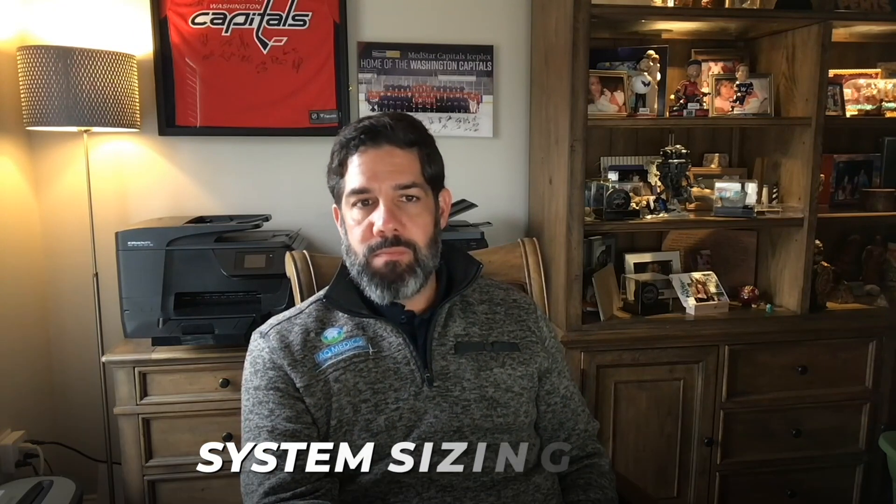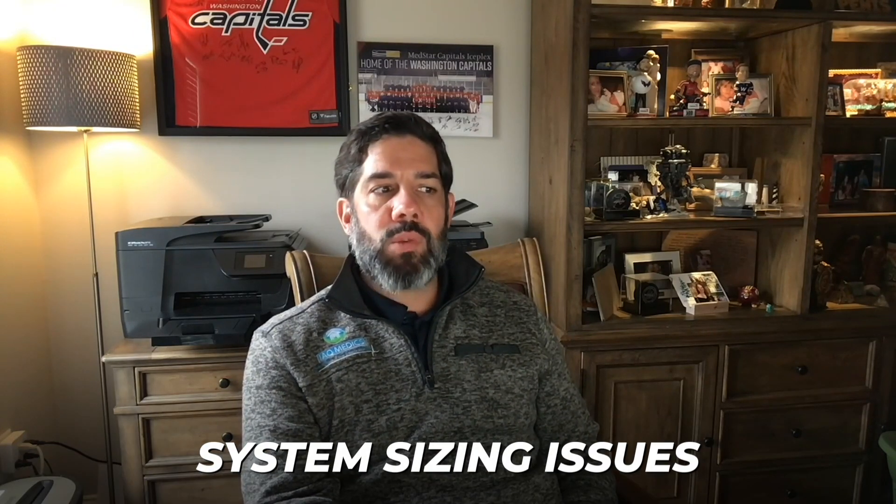It's a little bit of all of that. One of the biggest problems we probably find are system sizing issues — when clients have had additions put in and it's not calculated in, or if it's an older home predating a formal manual J load calculation being completed. That's when they can get into some issues, especially with a lot of these higher-efficiency systems that operate way differently. You could end up having ductwork that's sweating everywhere just because the system's either too big for it, or it's running too long at much colder temperatures and causing dew point to hit on the ductwork itself.